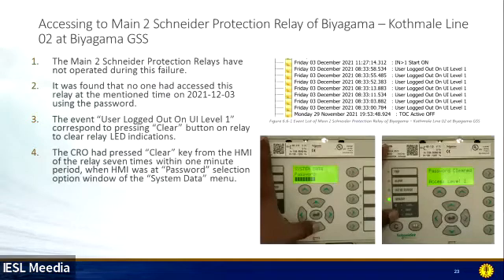the control room operator tried to erase some LED indications that had come up on the relay. He wanted to erase them. For that process, he pressed the clear button, and he pressed it while the relay menu was on the password selection menu. This is how the relay manufacturer has explained it.